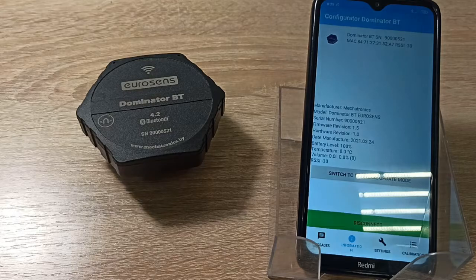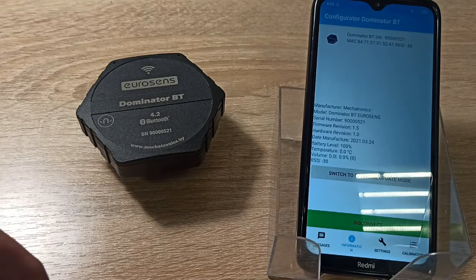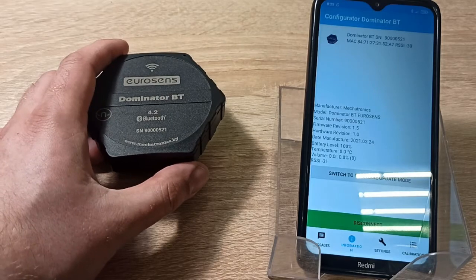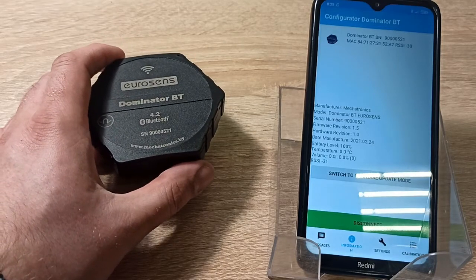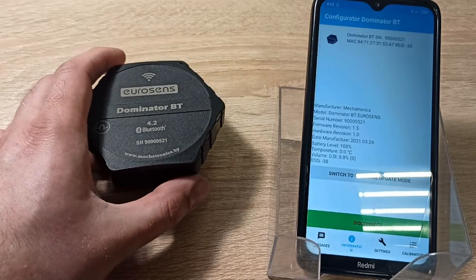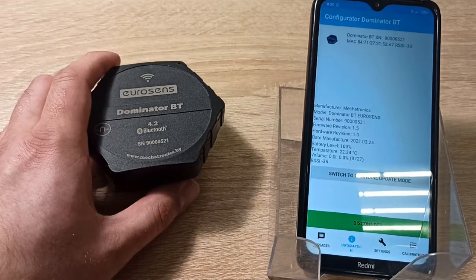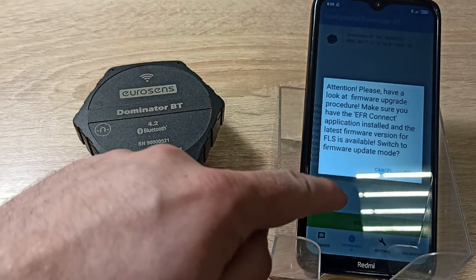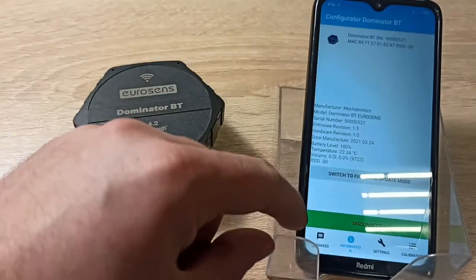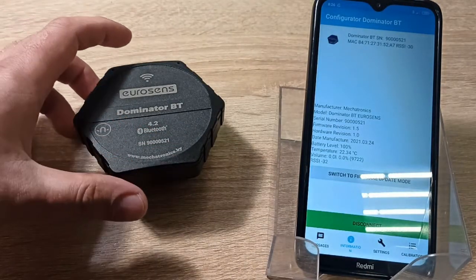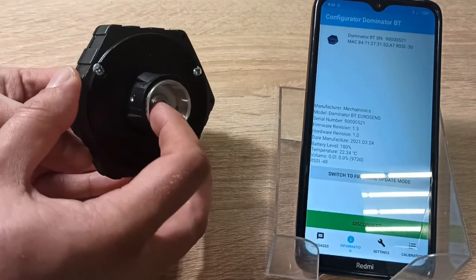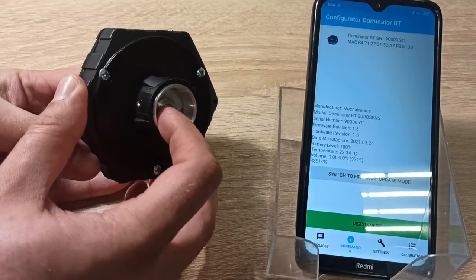In the information tab, the Configurator displays whether the sensor has entered configuration mode recently. To put the sensor into configuration mode, use the magnet and touch it to the magnet icon on the sensor case. Then open sensor details — note that the sensor doesn't send data every second, so you need to wait a bit.